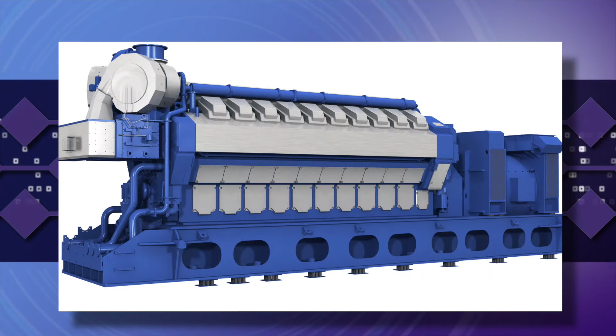The engines at Schofield will be very efficient. They will have a heat rate in the mid 8,000s, as in 8,000 BTUs per kilowatt hour. In addition, they provide benefits to the environment by being low water usage. The only water we'll be using on the site essentially is to make some urea, which will be used for emissions controls.